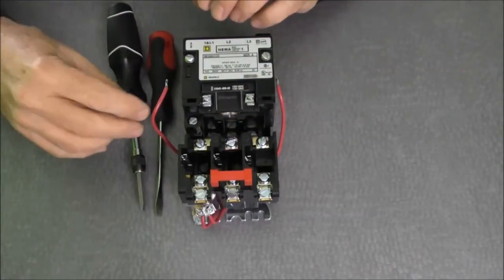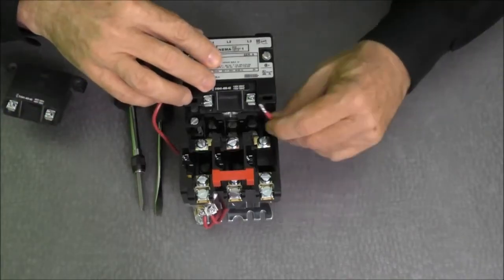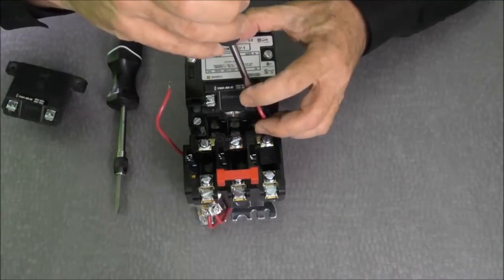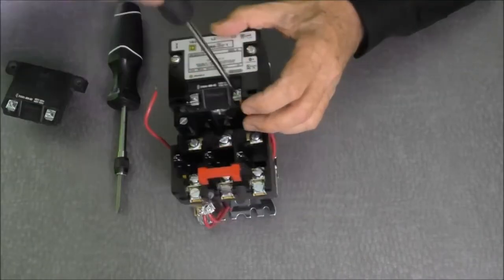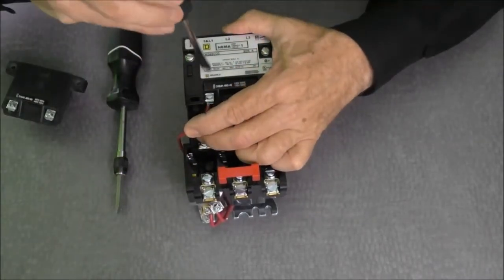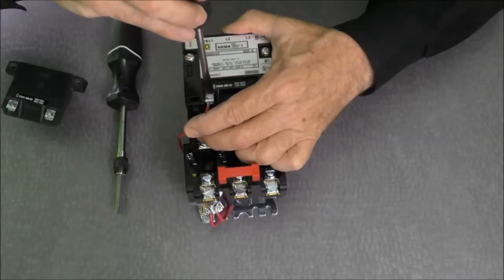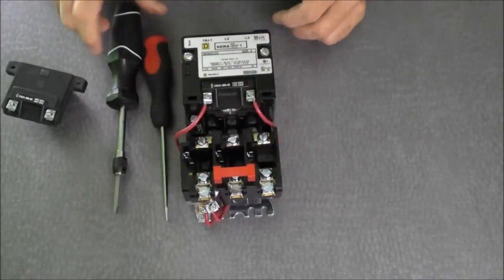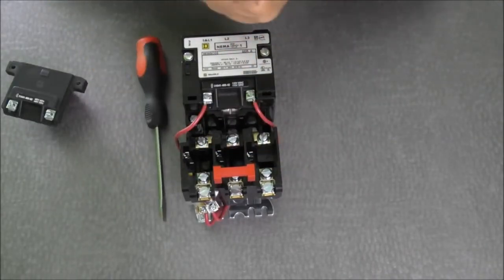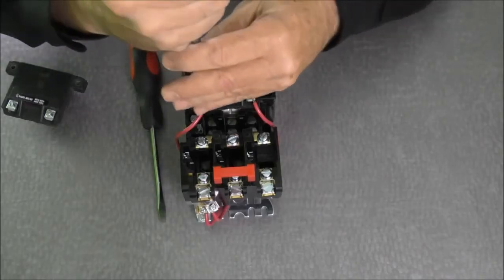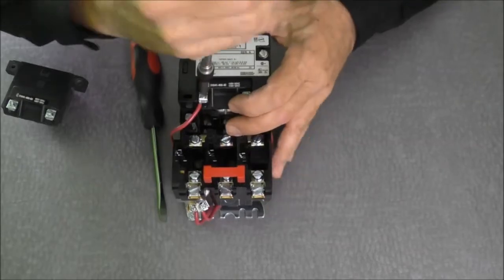The next thing I'll need to do is replace the wires for the coil. Again, I'm going to use a screwdriver initially to snug them down. We'll put the wires on both terminals. And these particular terminals have a 9 to 12 inch pound rating. So I'm going to get down to about 10 inch pounds. Then I'm going to torque it again. Once you hear the screwdriver ratchet, we know they're tight.